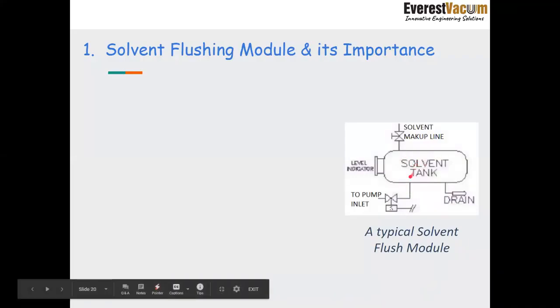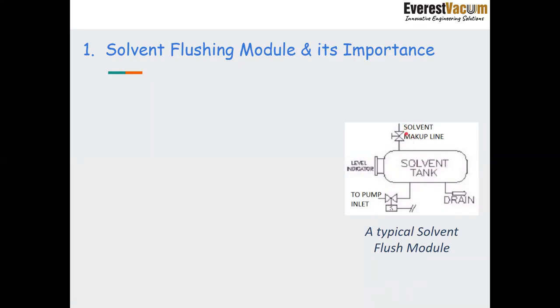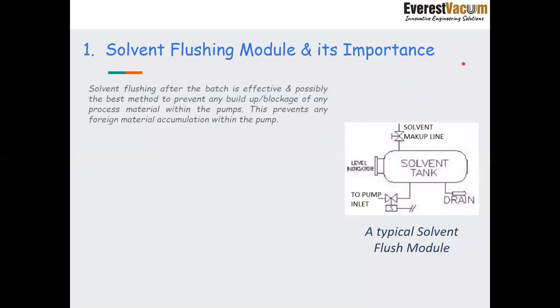There is one tank having a level indicator. Then there is a filling port from where you can pour the solvent into it. Then there is one small drain provided to clean the tank in case required. And this is the major operation: it is an actuated solenoid valve which connects directly to the pump inlet, from where the solvent enters into the dry screw vacuum pump to clean it out. So what is its importance? As mentioned, solvent flushing after the batch is very effective, and it is the best method available to clean out the pump of any contamination, any buildup, any blockage of the process material.